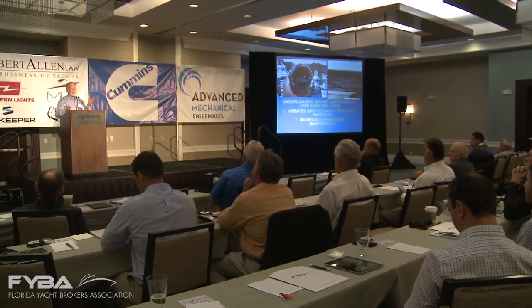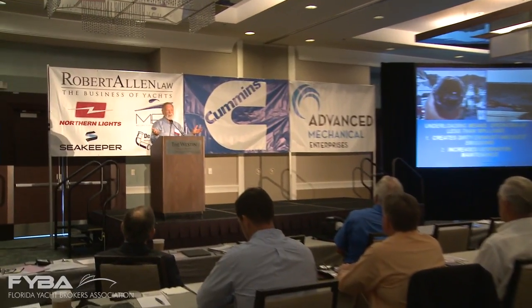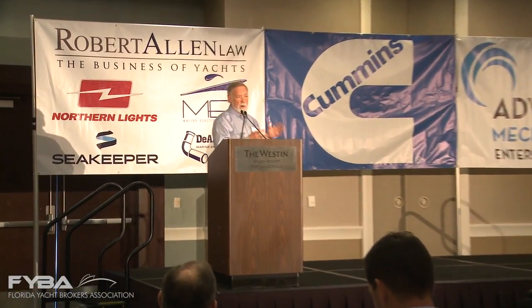Most people convert that. They want to know how many amps that is. Question we always get. So how do you figure out what it is? I'll give you a real simple way, keep the math simple. Let's pretend you have a 12 kilowatt generator. 12 kilowatts is 12,000 watts, okay? If you divide it by the voltage that you're taking the power out at, 120 volts, you get 100 amps. So 12 kilowatts gives you 100 amps at 120 volts. So half of that would be 50 amps. So we want to see that generator loaded to 50 amps. So that makes the math easy. Just divide the kilowatts by the volts that you're using, and then you can figure out how many amps are available.